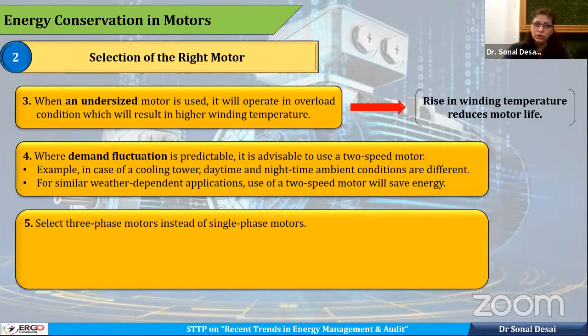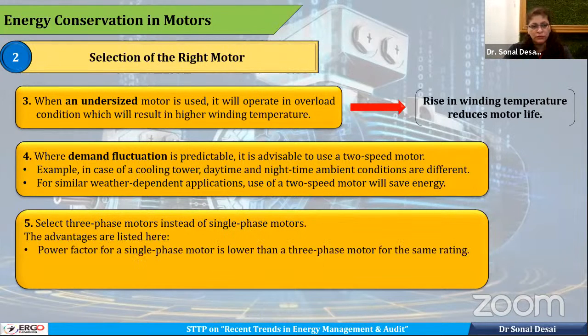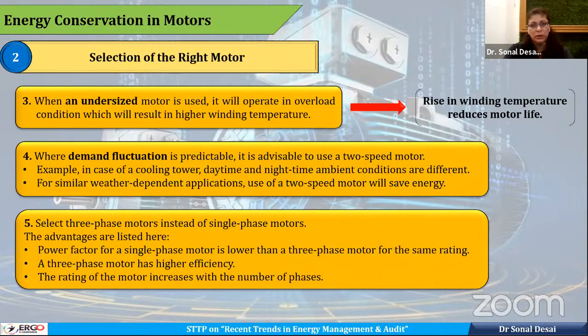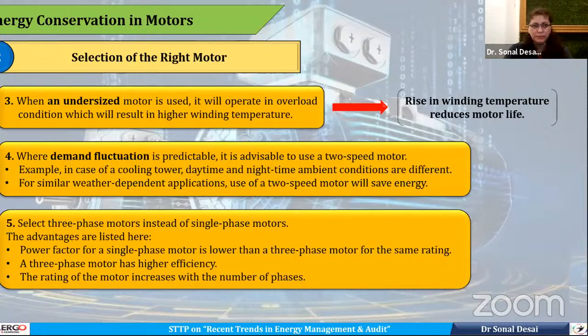Go with the 3-phase motor. A 3-phase motor will have a better power factor compared to a single-phase motor, and it will also have a higher efficiency. So wherever permissible, go with the 3-phase motor. The rating of motor increases with the number of phases. It is a basic fundamental.